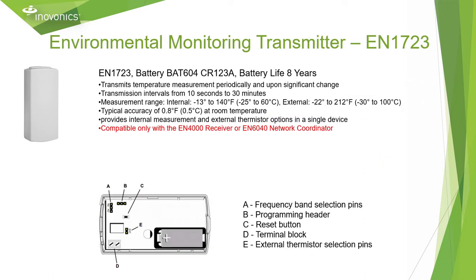The EN1723 provides internal measurement and external thermistor options in a single device. Like its sister transmitters, it will periodically send its temperature measurements upon significant change and can adjust the transmission intervals from 10 seconds to 30 minutes. It has the ability to measure a temperature range of -13 degrees to 140 degrees Fahrenheit with the internal sensor and -22 degrees to 212 degrees Fahrenheit with the external probe. It has an accuracy of 0.8 degrees Fahrenheit and has a battery life of 8 years.